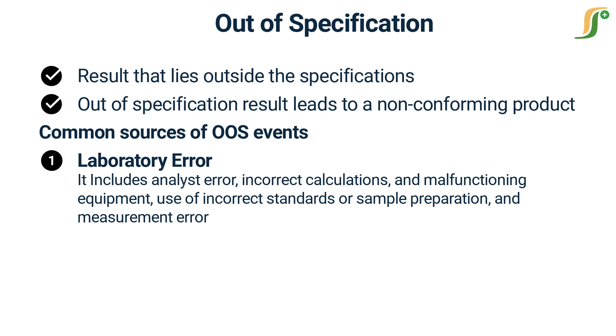Laboratory error should be relatively rare. Frequent errors suggest a problem that might be due to inadequate training of analysts, poorly maintained or improperly calibrated equipment, or careless work. Whenever a laboratory error is identified, the laboratory should determine the source of that error and take corrective action to prevent recurrence.